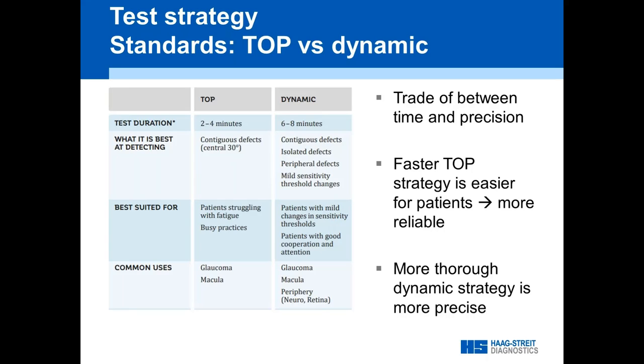The TOP strategy, on the other hand, is much faster, which has workflow advantages and is nicer for the patient. The TOP strategy starts with very bright stimuli — so the easy ones come first — and the dim stimuli that are barely visible come at the end of the test. This is really helpful for patients learning or patients struggling, because psychology is everything for reliable visual field results. Mathematically, Dynamic is more precise, but TOP is better for patients who really struggle — so it's a choice.